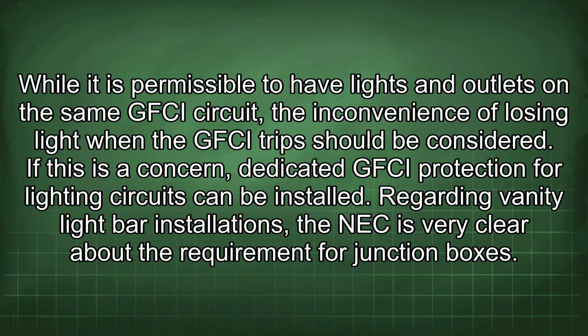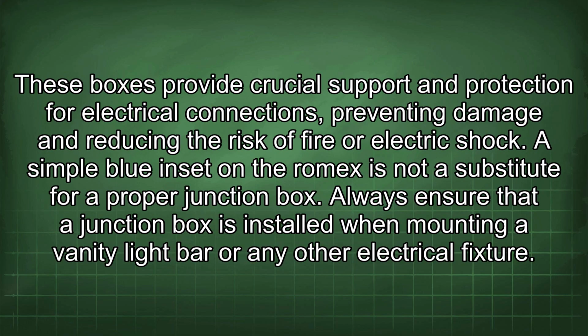Regarding vanity light bar installations, the NEC is very clear about the requirement for junction boxes. These boxes provide crucial support and protection for electrical connections, preventing damage and reducing the risk of fire or electric shock. A simple blue inset on the Romex is not a substitute for a proper junction box. Always ensure that a junction box is installed when mounting a vanity light bar or any other electrical fixture.